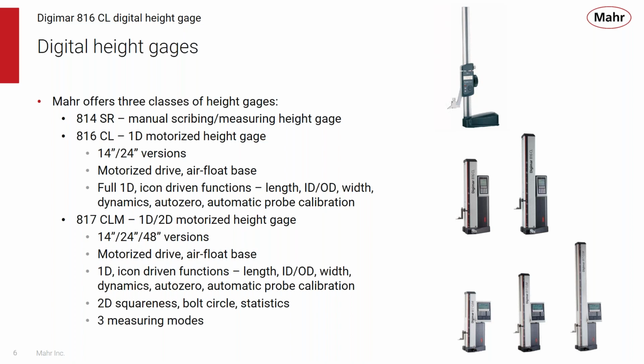And then on the higher end is our 817 CLM, which is a 1D or 2D motorized height gauge in three versions up to 48 inches. Again, it's motorized drive and air float base. It offers 1D measurements for length, IDs and ODs, dynamics, auto zero, probe calibration, etc. But it also has 2D functions for doing things like squareness and bolt circle patterns, plus it has some statistical features. And it comes with three measuring modes to make it just a little bit easier to use. But today we're going to concentrate on the 816 CL, which is our product of the month, and we'll talk about some more of the features of the 816 CL.